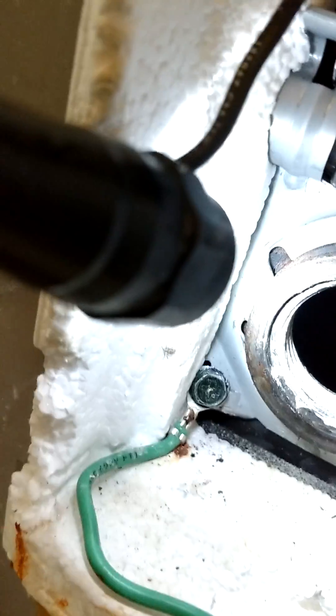Now that mountain that used to be in there is no longer there — I don't see anything. All I did was give a little hook tip to the hose and went side to side, tapping around. At that point I'd say 95 to maybe 98% of it is gone. You can see the back now and see the little reflection in there.